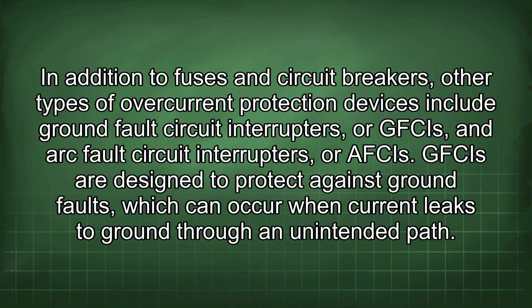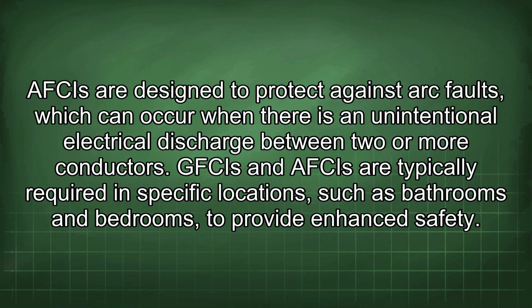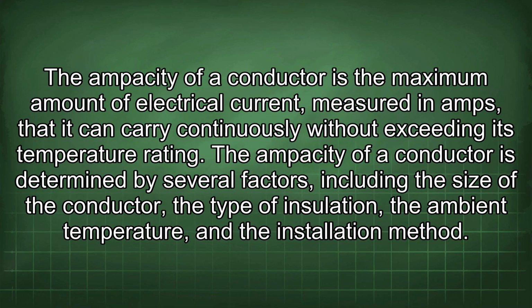GFCIs are designed to protect against ground faults, which can occur when current leaks to ground through an unintended path. AFCIs are designed to protect against arc faults, which can occur when there is an unintentional electrical discharge between two or more conductors. GFCIs and AFCIs are typically required in specific locations, such as bathrooms and bedrooms, to provide enhanced safety. The ampacity of a conductor is the maximum amount of electrical current, measured in amps, that it can carry continuously without exceeding its temperature rating.